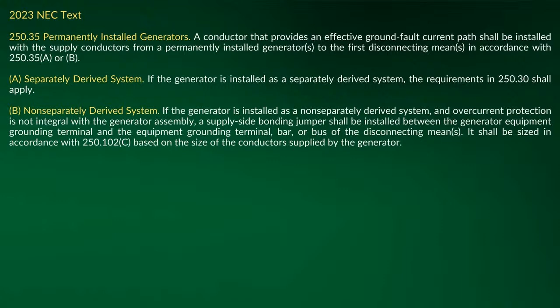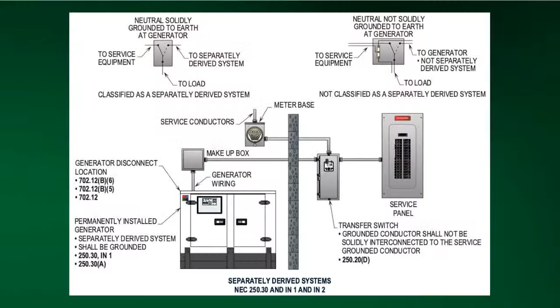There's a problem in the language, in my opinion, because I've always been taught once you establish that overcurrent protection for that building, that's your first point of disconnection. Yeah, and that was kind of my reluctance with the whole argument with Justin. Whichever one Justin was talking about, it was covering the supply side of the equipment. And it causes problems because you're like, oh, okay, it has to be a service rated transfer switch. Okay, well, it's service rated, but it's not technically on the supply side.